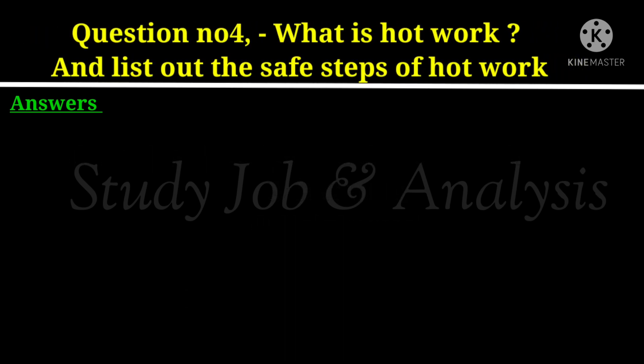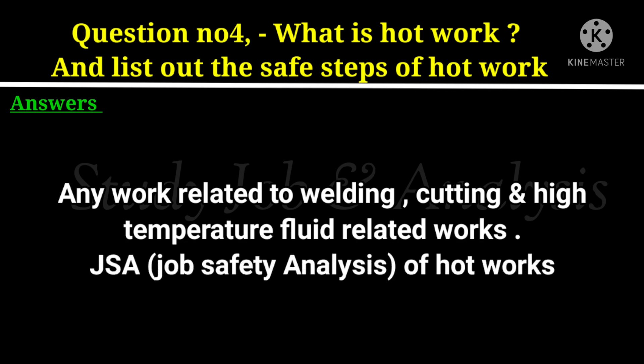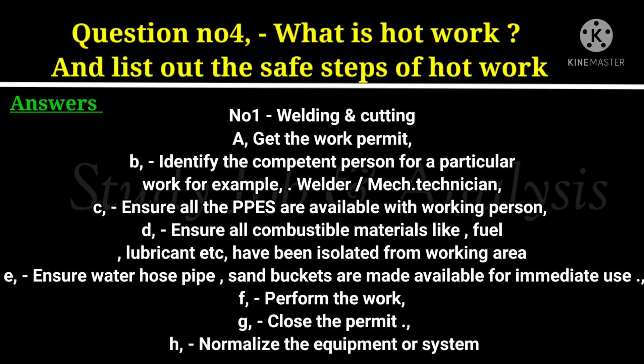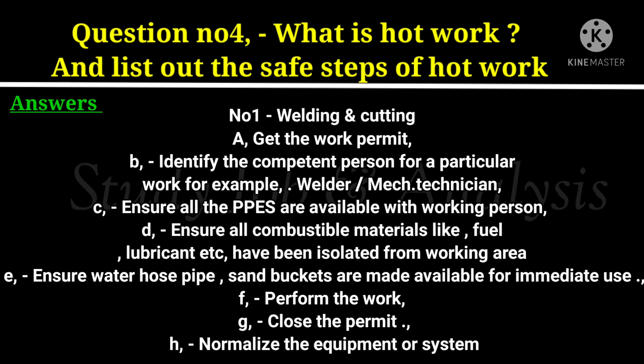Question number 4: What is hot work? And list out the safe steps of hot work. Any work related to welding, cutting, or high temperature fluid related works. JSA — Job Safety Analysis of hot works. Number 1: Welding or cutting. A. Get the work permit. B. Identify the competent person for a particular work, for example welder, mech technician. C. Ensure all the PPEs are available with the working person. D. Ensure all combustible materials like fuel, lubricant, etc. have been isolated from the working area. E. Ensure water hose pipe and sand buckets are made available for immediate use. F. Perform the work. G. Close the permit. H. Normalize the equipment or system.